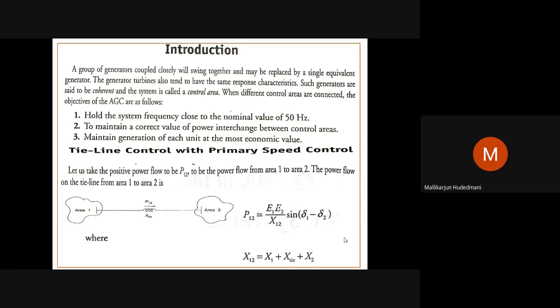It necessitates the interconnected operation or borrowing of power, or, the other way, demand side strategies: removal of load, disconnection, managing the load in an effective manner, in a time staggered manner. For that, AGCs, when they are in interconnected operation, should maintain the correct value of the interchange between the areas, and maintain generation of each unit at the most economic value. See, this is a very important aspect.